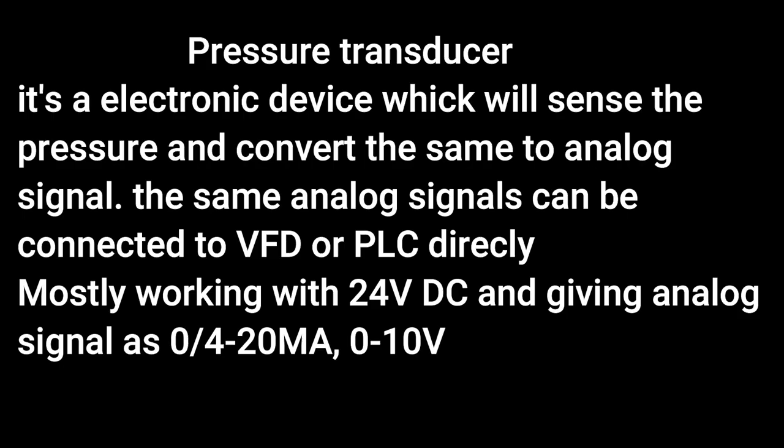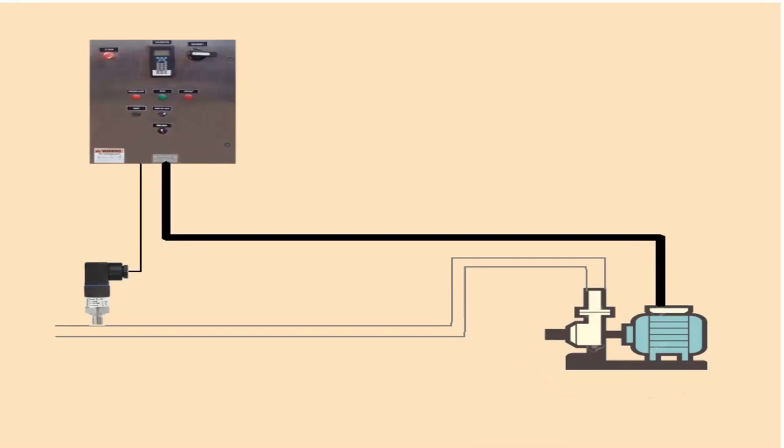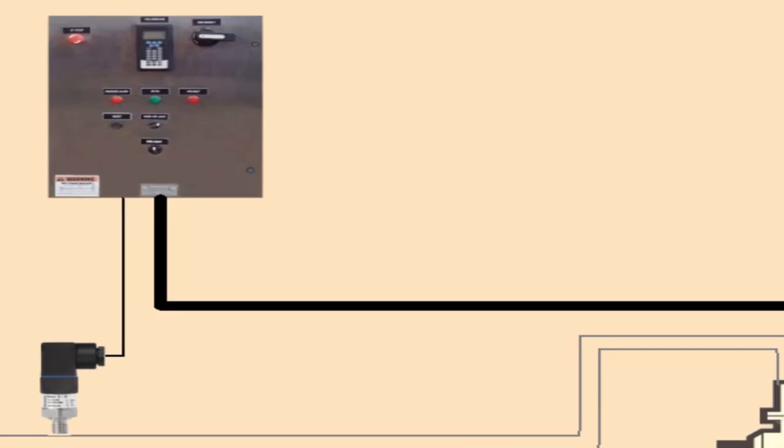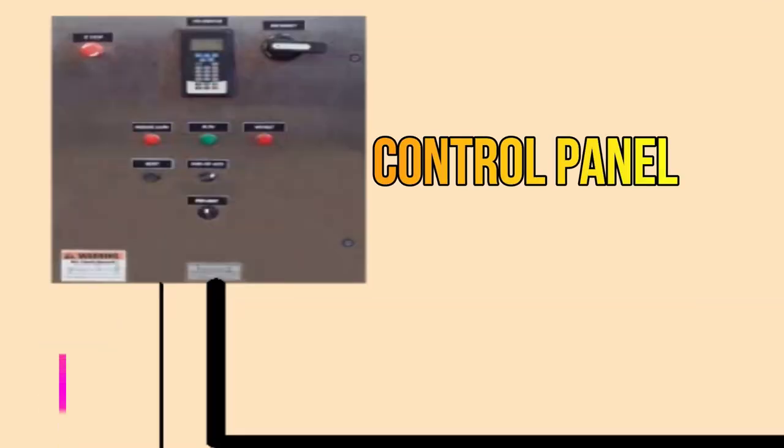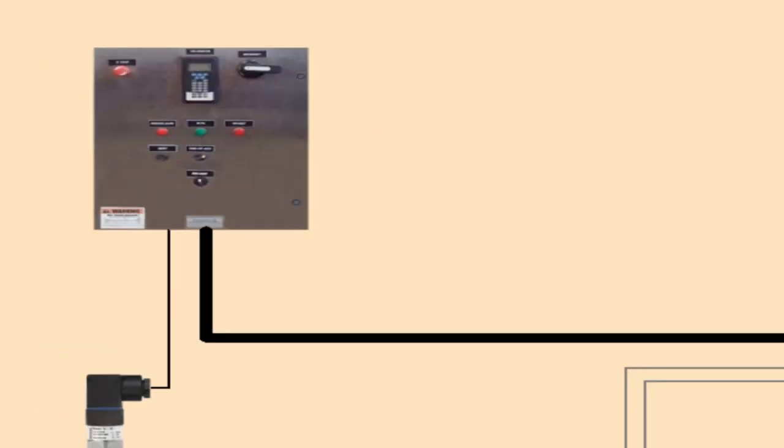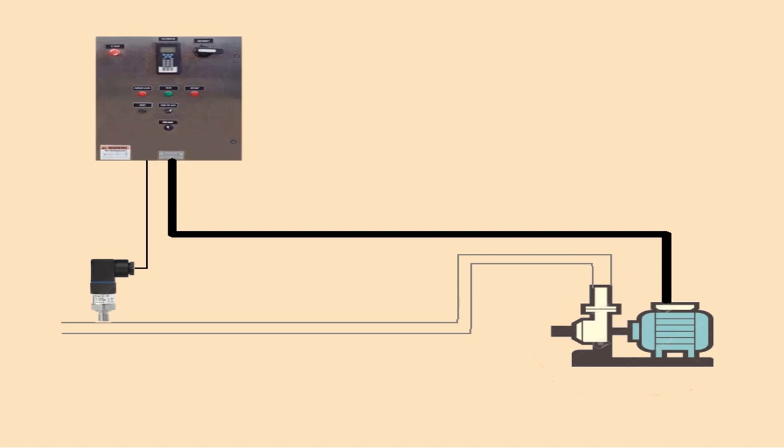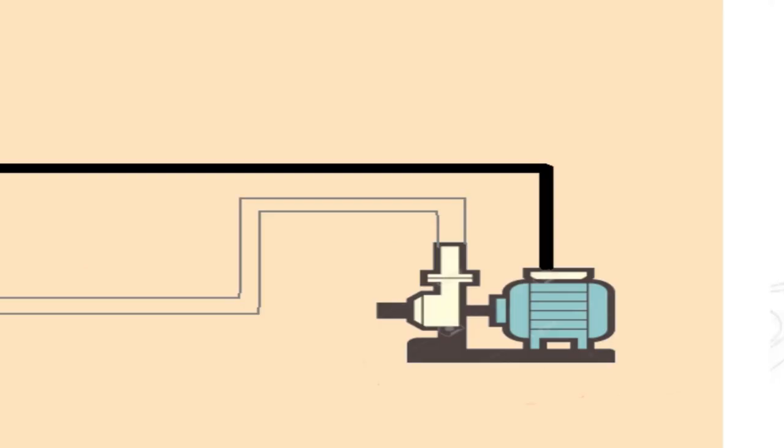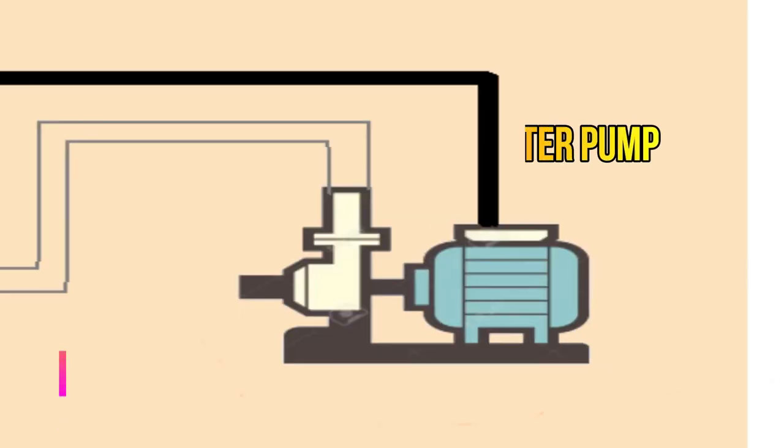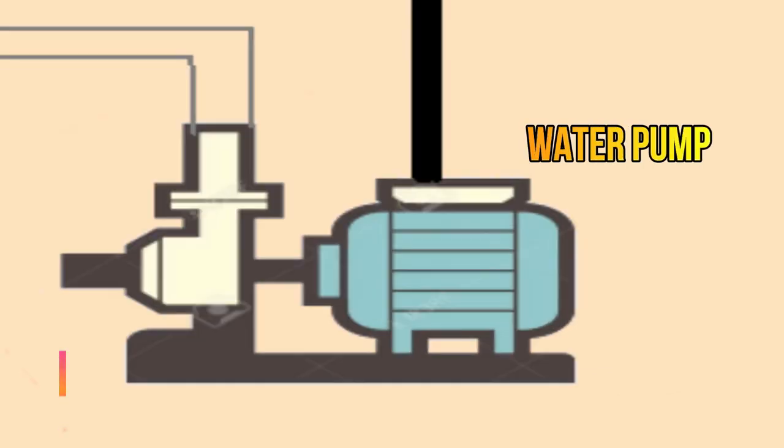Pressure transducer, also called pressure transmitter, is an electronic equipment which will sense the direct pressure and convert the pressure into analog signal like 0 to 10 volt or 4 to 20 milliampere or 0 to 20 milliampere.